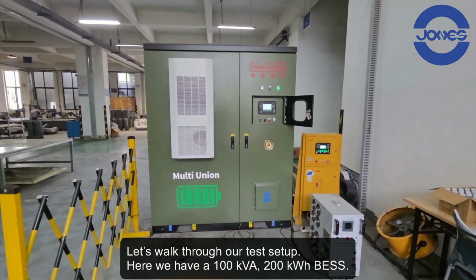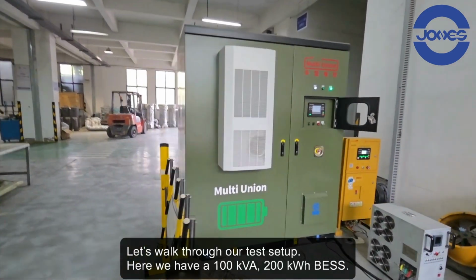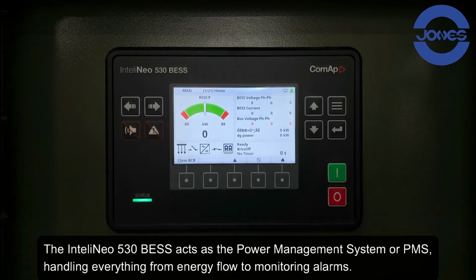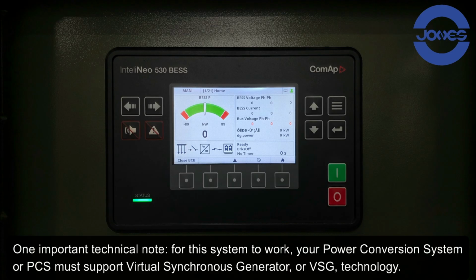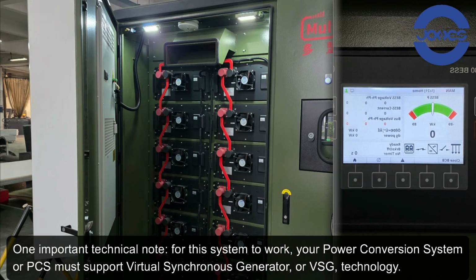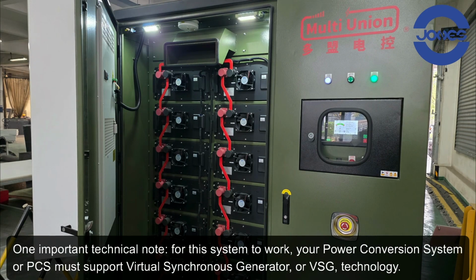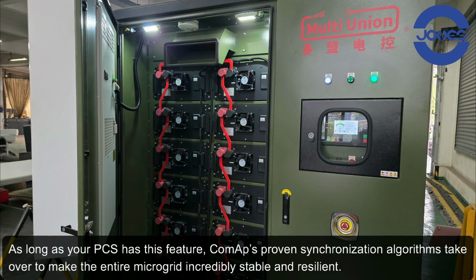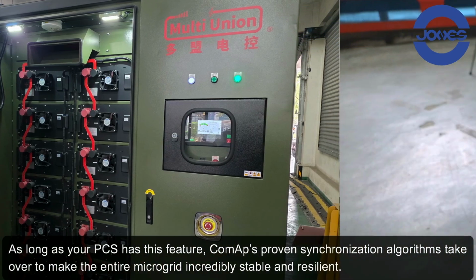Let's walk through our test setup. Here we have a 100 kVA, 200 kWh BESS. The InteliNeo 530 acts as the power management system, or PMS, handling everything from energy flow to monitoring alarms. One important technical note: for this system to work, your power conversion system, or PCS, must support Virtual Synchronous Generator, or VSG technology. As long as your PCS has this feature, ComAp's proven synchronization algorithms take over to make the entire microgrid incredibly stable and resilient.